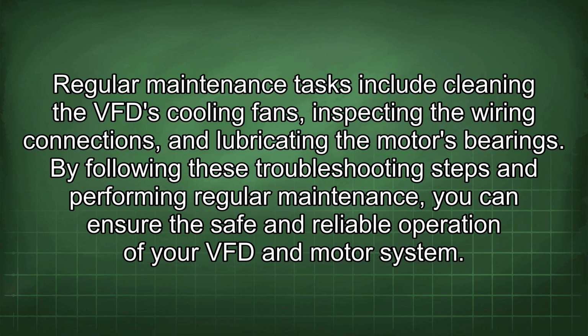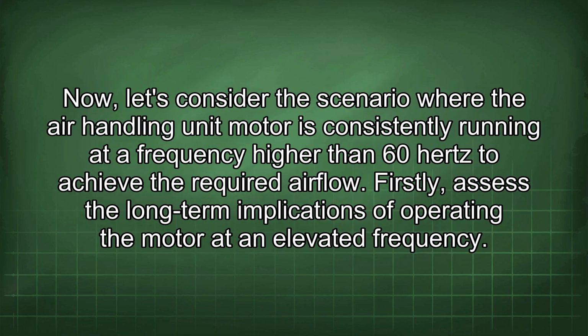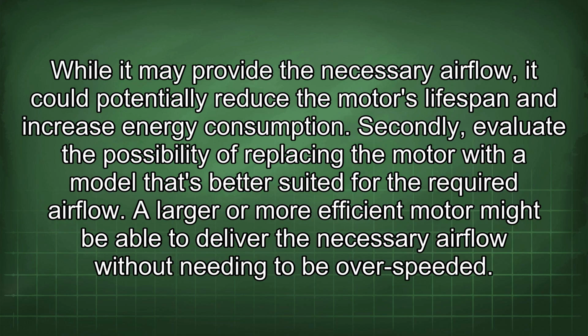and motor system. Now, let's consider the scenario where the air handling unit motor is consistently running at a frequency higher than 60 Hz to achieve the required airflow. Firstly, assess the long-term implications of operating the motor at an elevated frequency. While it may provide the necessary airflow, it could potentially reduce the motor's lifespan and increase energy consumption. Secondly, evaluate the possibility of replacing the motor with a model that's better suited for the required airflow. A larger or more efficient motor might be able to deliver the necessary airflow without needing to be overspeeded.